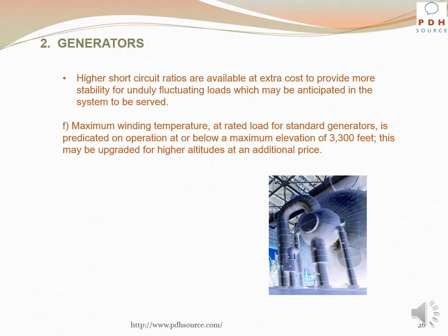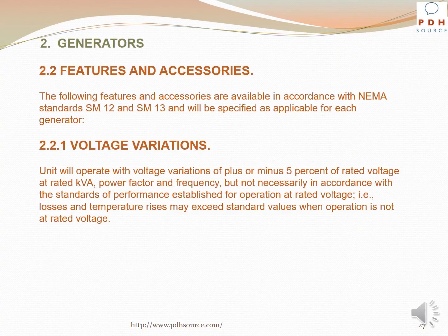Maximum winding temperature at rated load for standard generators is predicated on operation at or below a maximum elevation of 3,300 feet. This may be upgraded for higher altitudes at an extra cost. The following features and accessories are available in accordance with NEMA standards SM12 and SM13 and will be specified as applicable for each generator.